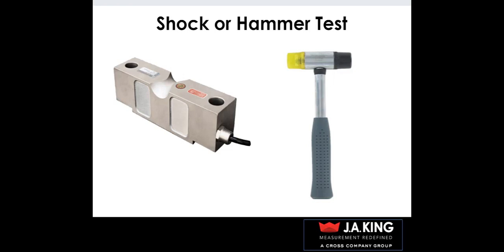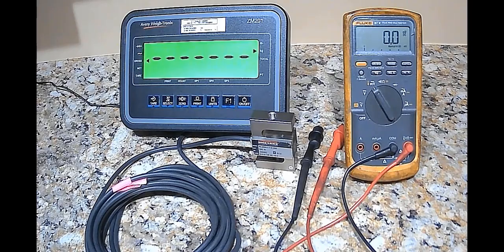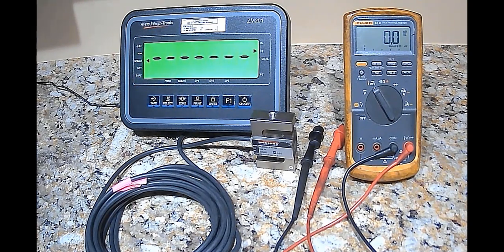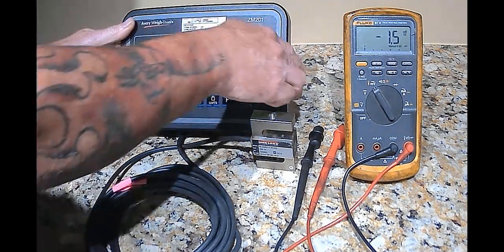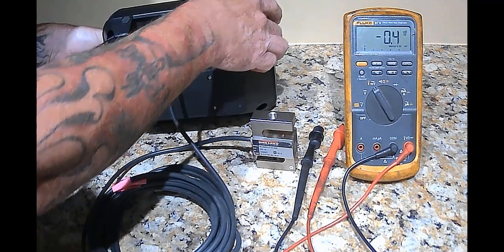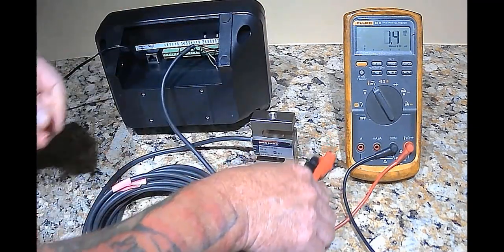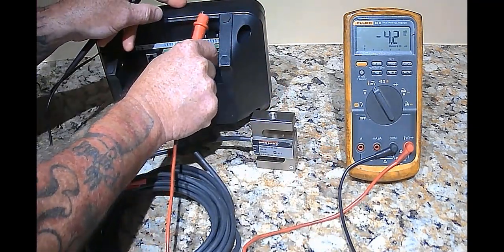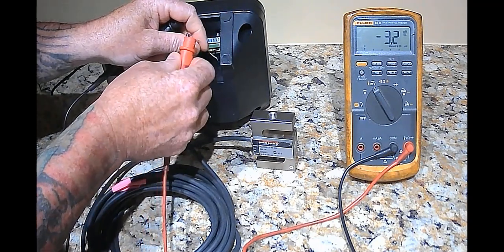For the shock test, if using a hammer, make sure it is a rubber mallet only. Do not use metal hammers when doing a shock test. With the cell or cells connected to the excitation terminals and the signal wires disconnected, put the multimeter probes on the positive and negative signal wires for the cell to be tested.